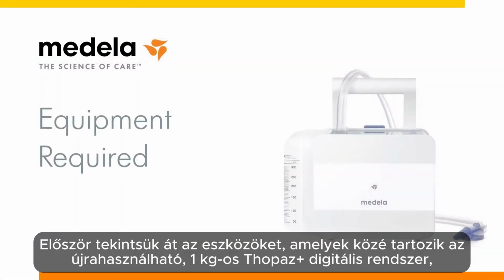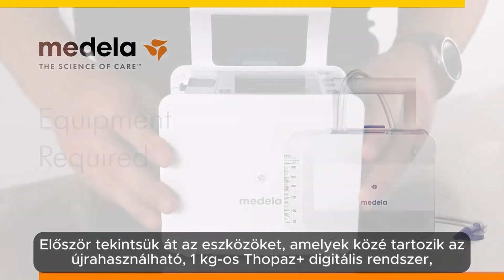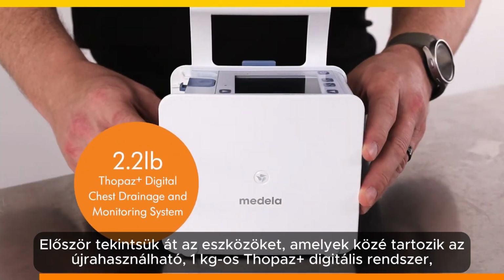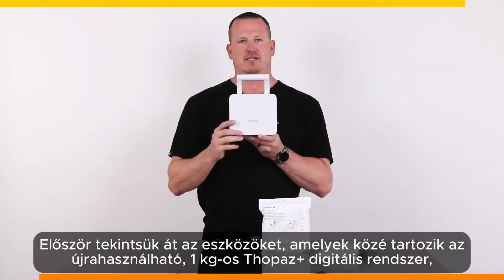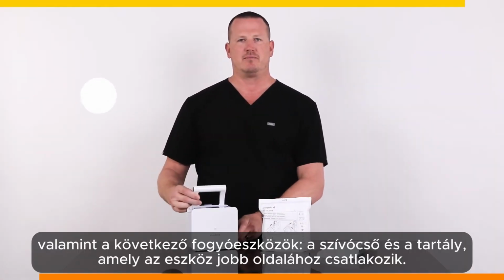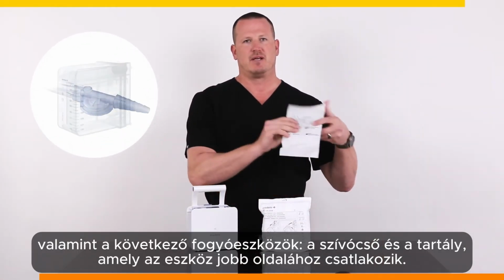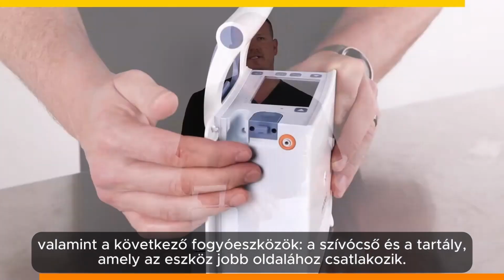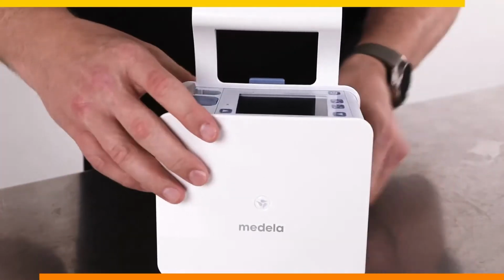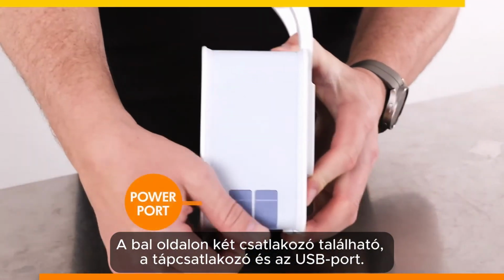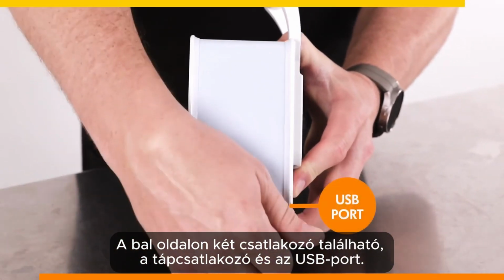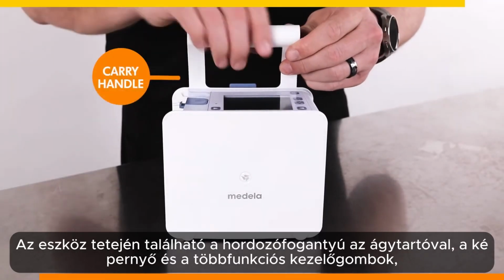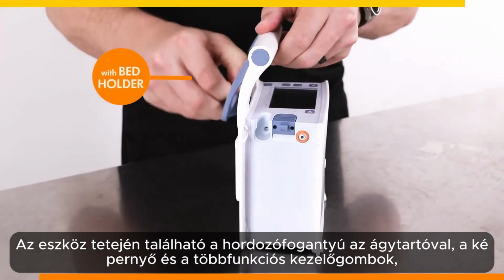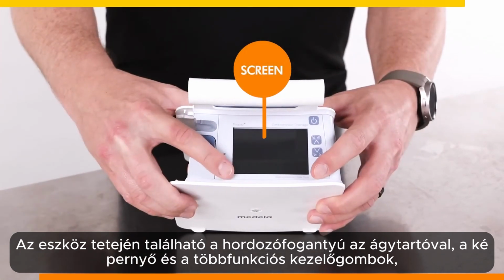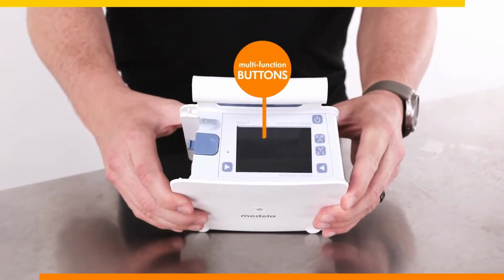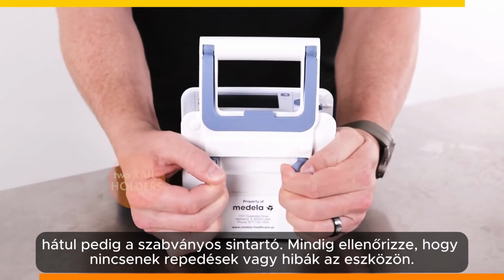First, let's review the equipment required for setup, which includes the reusable 2.2-pound TOPAZ Plus digital chest drainage and monitoring system, and the following consumable items: the tubing and the canister, which will attach to the right side of the device. On the left side of the device are two ports, the power port and the USB port. On the top of the device is the carrying handle with the bed holder, the screen, and multifunction operational buttons. And on the back you will find two rail holders.